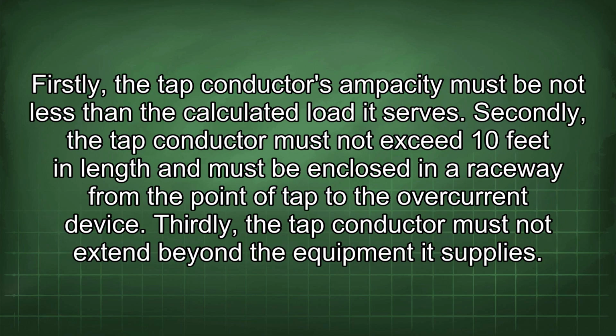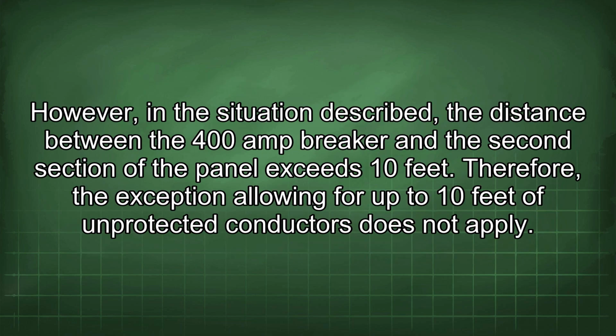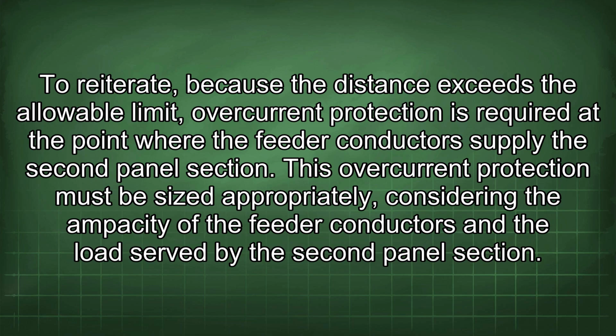provided certain conditions are met. Firstly, the tap conductor's ampacity must be not less than the calculated load it serves. Secondly, the tap conductor must not exceed 10 feet in length and must be enclosed in a raceway from the point of tap to the overcurrent device. Thirdly, the tap conductor must not extend beyond the equipment it supplies. However, in the situation described, the distance between the 400 amp breaker and the second section of the panel exceeds 10 feet. Therefore, the exception allowing for up to 10 feet of unprotected conductors does not apply. To reiterate, because the distance exceeds the allowable limit, overcurrent protection is required at the point where the feeder conductors supply the second panel section.